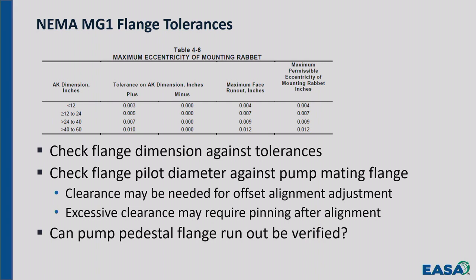The second problem is most of these vertical turbine pumps, almost all of them, the pump rotor hangs on the motor. So until the motor is on and the coupling is on, the impellers are sitting on the housing and you can't turn the shaft. So how do you check the runout on the pump flange? It's really a problem. I don't have a real good solution for that. I can tell you what some folks have done, but it's not a universal solution.